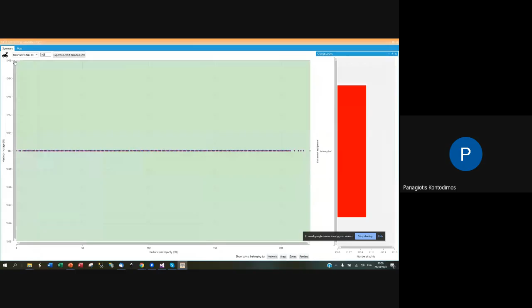I can see, for example, what happens with the voltage. Very quickly, my voltage is dropping. You see, the more I increase the electric vehicle penetration, the voltage goes down statistically. I reach a point at 170 kilowatts of total penetration where all the scenarios I tested are violating my voltage limit. Therefore, I cannot increase the power more than that in terms of voltage.